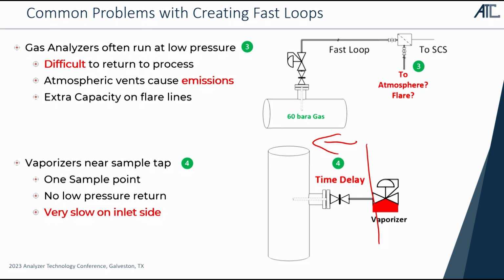And the problem is, if we're putting vaporizers out near the sample tap, near a process pipe where everything is one pressure, we have no low pressure return. And so these are going to run very, very slow on the inlet side. I think I do the calculations on a slide coming up, or I talk about the calculations on a slide coming up. But if that vaporizer is sitting on a 2-inch pipe nozzle that doesn't have a probe in it, you'll have about an hour or an hour and a half of time delay just to try to clear the pipe nozzle. Put a probe in, you might get it down to 20 minutes. But we're going to talk about a way to be able to do this a lot faster.